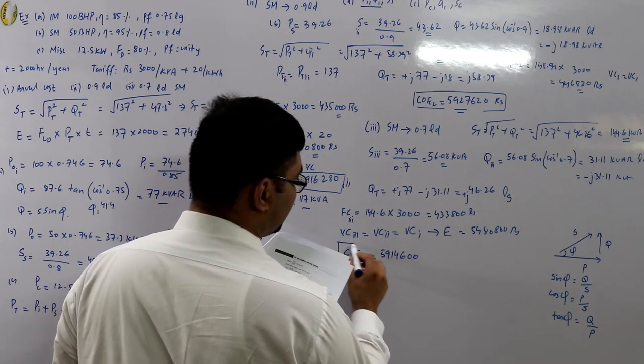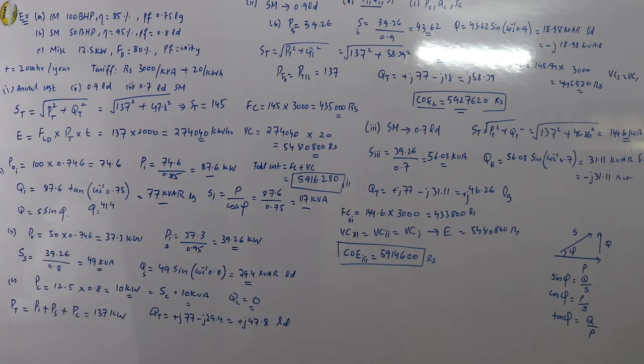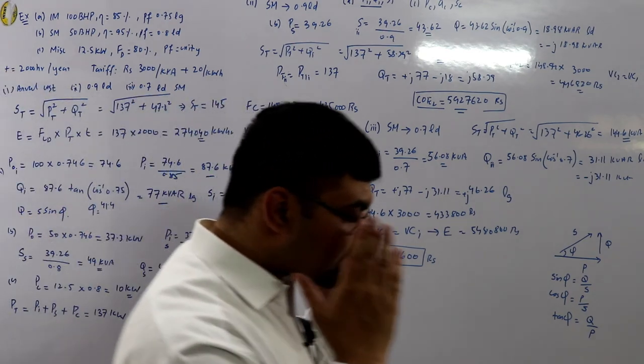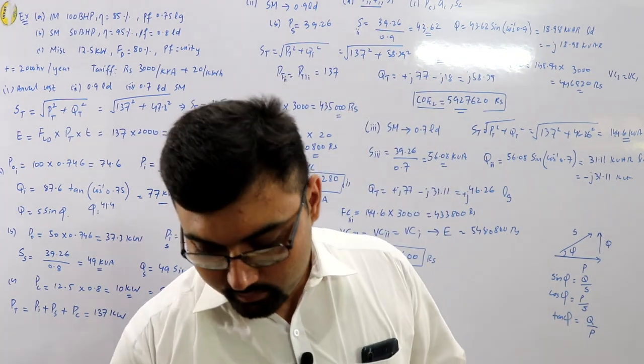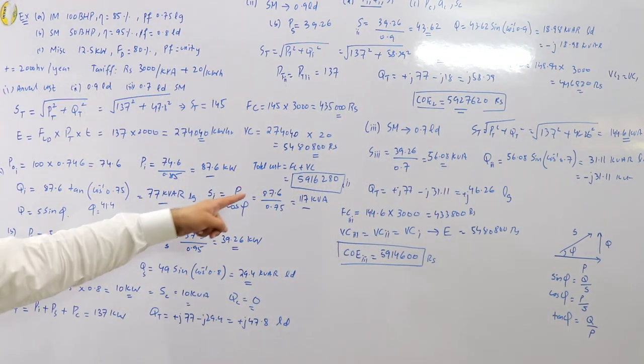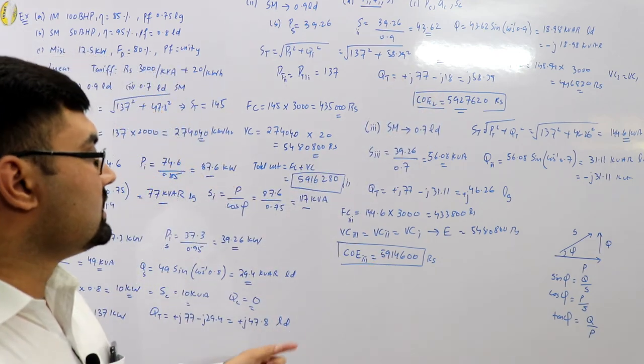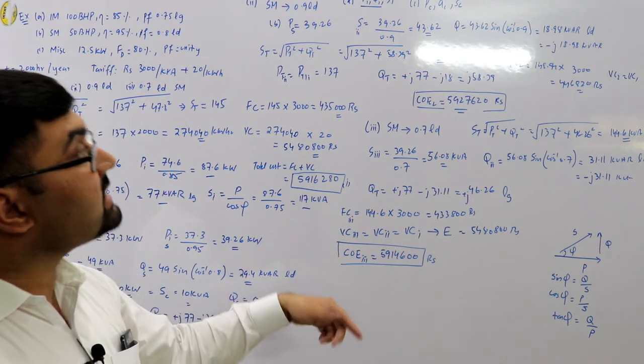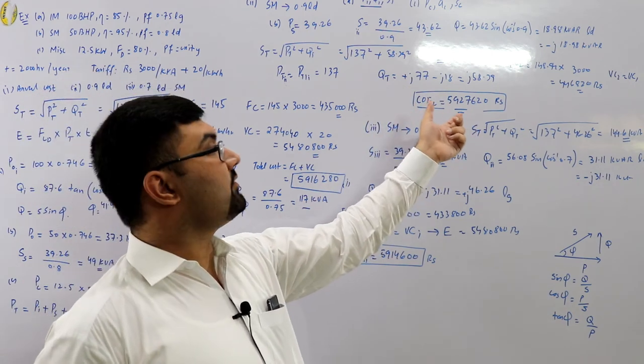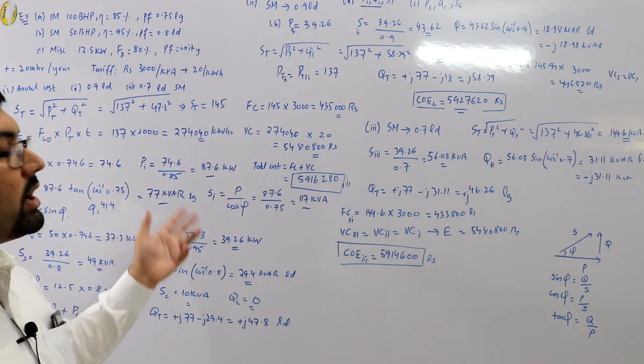By changing the excitation of the synchronous machine, we play with the power factor, and consequently the kVA and cost change. Comparing: Case 1 (0.8 leading) ≈ 5,916,280 rupees; Case 2 (0.9 leading) ≈ 5,927,620 rupees — maximum cost; Case 3 (0.7 leading) ≈ 5,914,600 rupees — minimum cost.